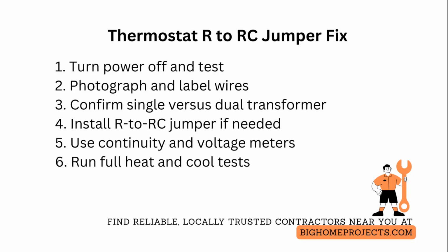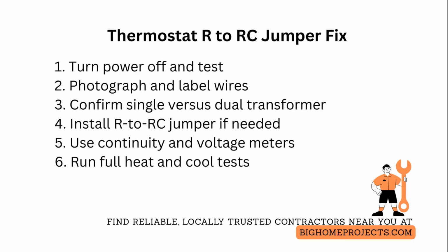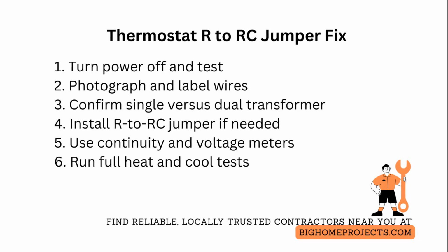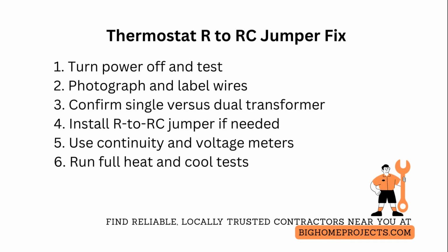If your thermostat has only one transformer, the R terminal provides the 24-volt supply, and RC must be tied to it with a short jumper, so the cooling relay sees power. Always turn power off at the breaker and confirm with a non-contact voltage tester before touching wires, then photograph the old wiring and label each conductor so you can restore or compare later.